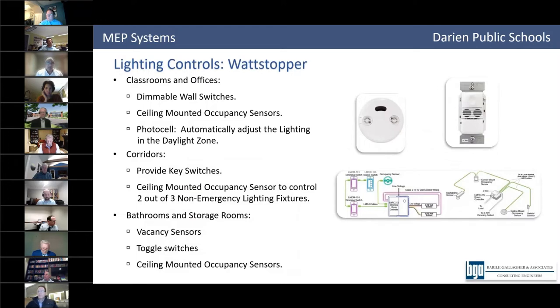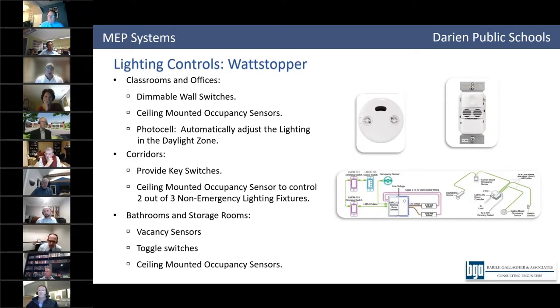For lighting controls, we're looking to use Watt Stopper as the control system. For classrooms and offices, we're looking to have dimmable wall switches, ceiling mounted occupancy sensors, and photo cells that will automatically adjust lighting in the daylight zones, mostly in classrooms. Any place with windows that has over 150 watts of lighting will have this feature installed.